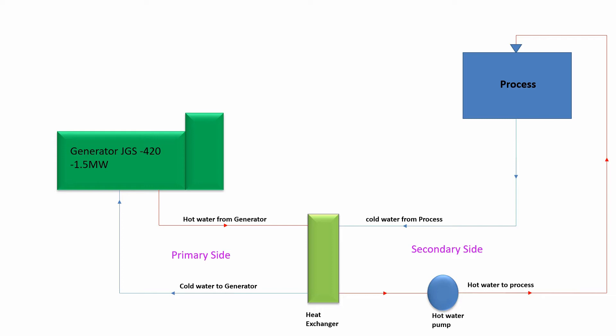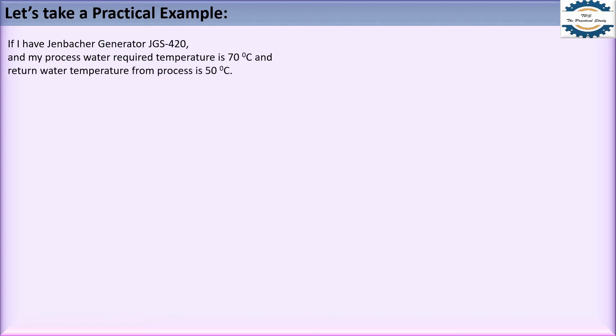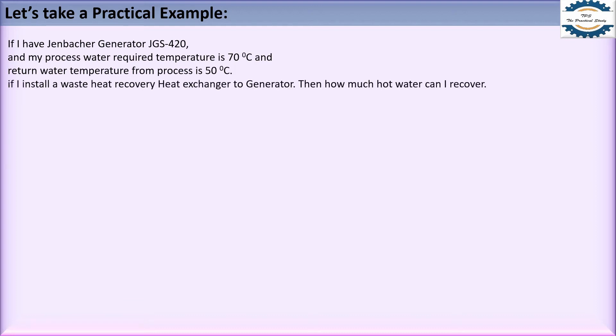Now the question is how this calculation can be done. For understanding, let's take a practical example. We have a JGS420 Jenbacher generator. Our process water required temperature is 70°C, and the cold water taken from the process is 50°C. If we install a waste heat recovery heat exchanger on the generator to use its waste heat, how much hot water can we recover?